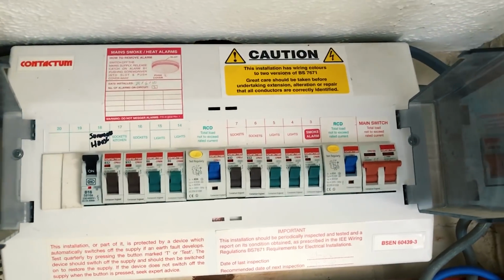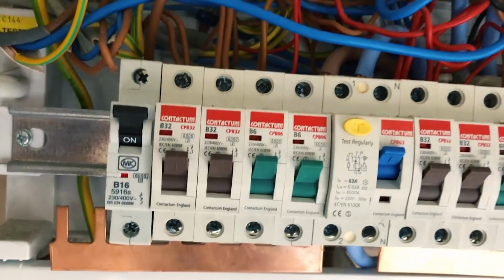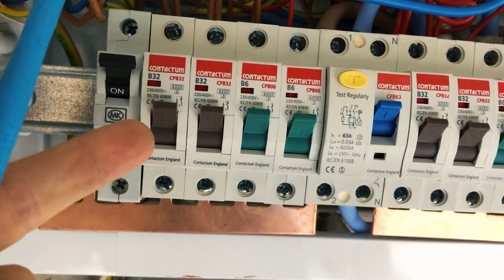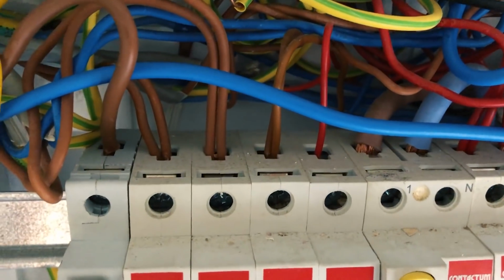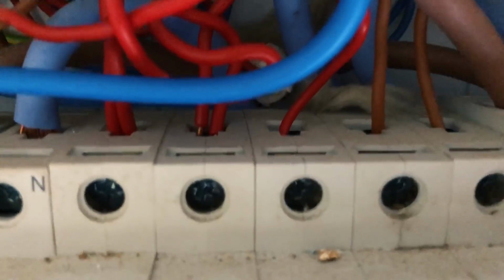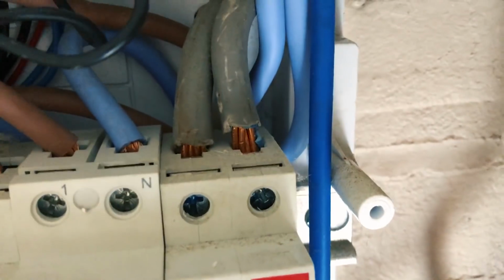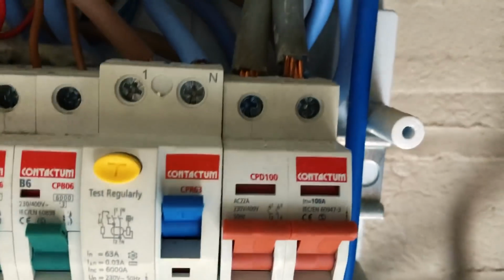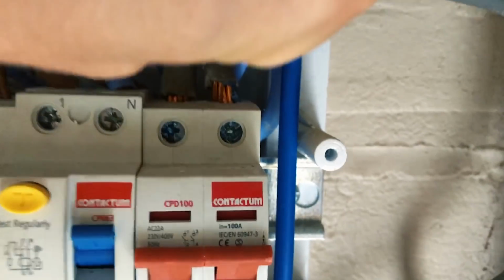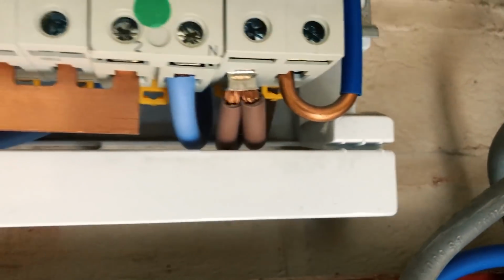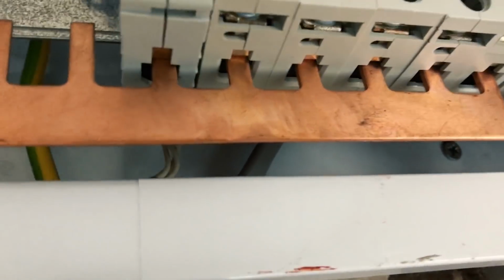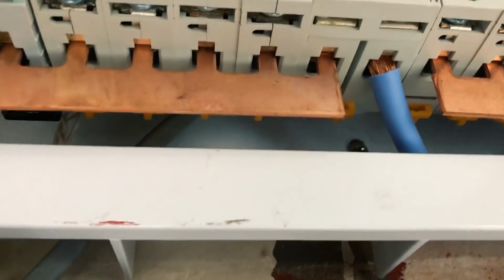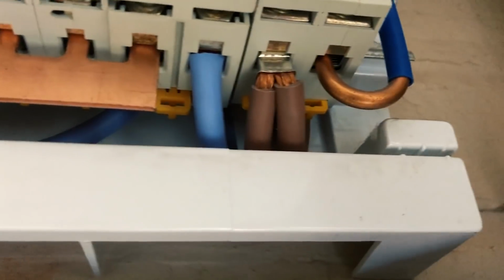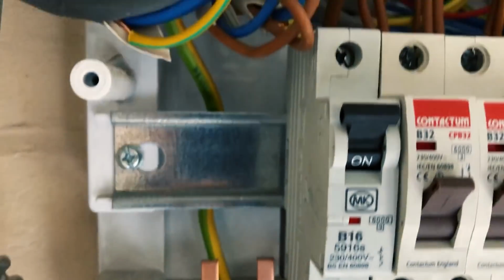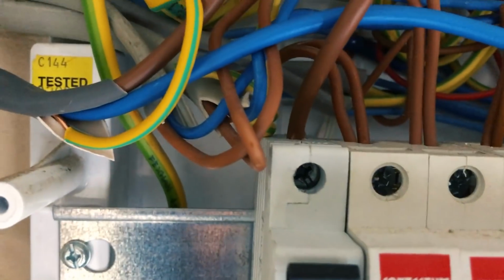Here's the consumer unit, and the circuit that has the problem is the kitchen sockets, labelled number 17. I've taken the cover off, and you can see this is the circuit with the problem. Looking above the circuit breakers, there doesn't seem to be any heat damage, though those tails are an absolute bodge. Apart from that, that's not obviously what's causing the fault. They are tight, it's just that they're quite far out of the connections. No obvious overheating or issues here. So that's the first thing I always check, the busbar connections and outgoing connections, to make sure there's nothing obvious there. But so far I can't see anything obvious with this particular circuit.